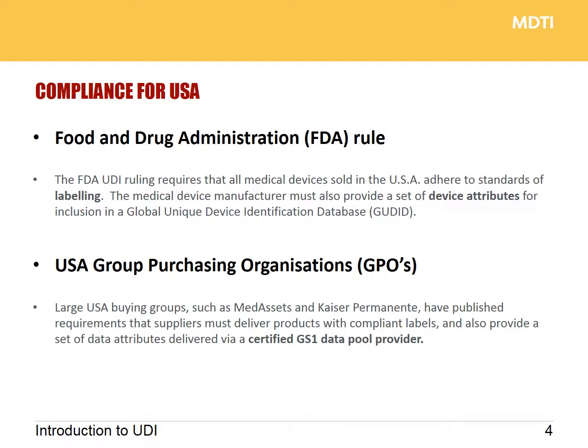So if we start with compliance for the USA, the Food and Drug Administration rule requires all medical devices sold in the US to adhere to GS1 labeling and also provide a set of data attributes to what they call the GUDID. Please always bear in mind that large US group purchasing organizations — Kaiser Permanente, Med Assets — have also published their own requirements which go far in excess of the FDA database. They essentially want manufacturers, if you supply to them, to deliver data via a certified GS1 data pool provider.